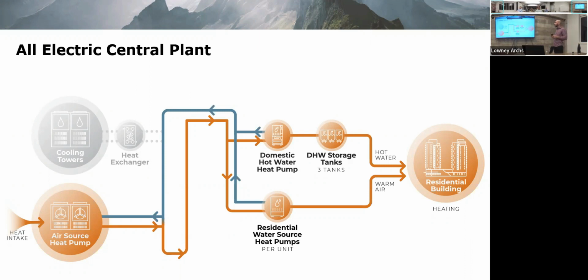measures. Yeah. And one thing about domestic hot water heat pumps: if you have an instantaneous water heater, it could be electric resistance or gas, you probably don't have large storage tanks. For centralized domestic hot water heating systems, if they're gas, you usually have storage tanks right now. But with heat pumps, what we're seeing is that the requirement for storage tanks is a lot bigger now because they don't act as fast. The heat pumps don't act as fast as other system types.